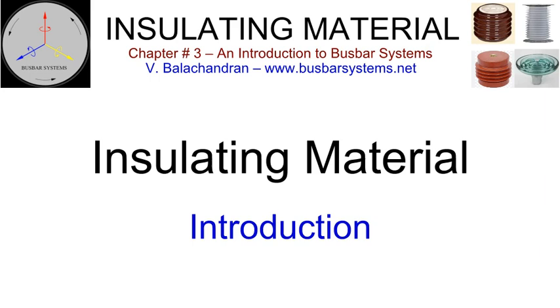Considerable research in the field over the past century in organic insulation has resulted in the development of synthetic resins: epoxy, polyester, cycloaliphatic, polyurethane, that had the desired properties. Glass-reinforced resin components such as dough molding compound, sheet molding compounds, pultrusions, and filament wound components were developed. Composite insulators are replacing them increasingly in outdoor applications as in post insulators, housings of switchyard equipment, and transmission line insulation. Films and tapes were developed to meet the ever-increasing demand for better thermal and dielectric properties in the transformer and motor industries. These have now been adopted in the switchgear and busbar systems industry as well.